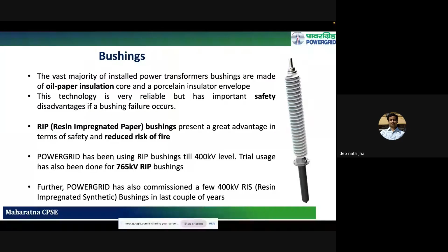We have been using resin impregnated bushings up to 400 kV level. Now trial uses for the same have also been done at 765 kV levels. And now there is also technology to remove the paper inside the bushings, because we have used those bushings with resin impregnated synthetics. So instead of normal paper, a synthetic compound is used and then again filled with resins to make the bushings more fireproof or more fire resilient.